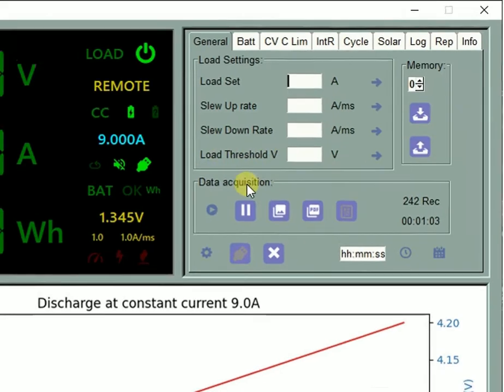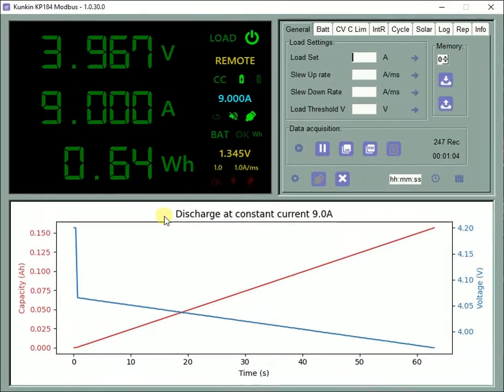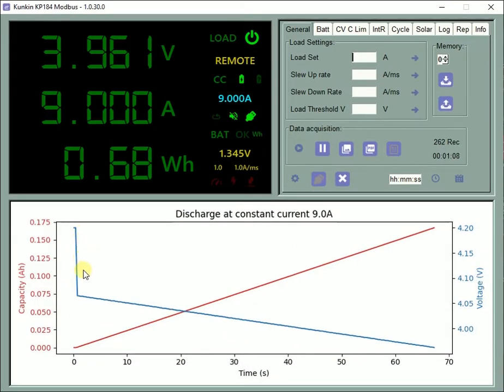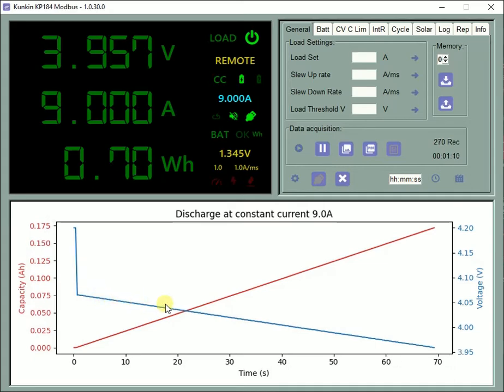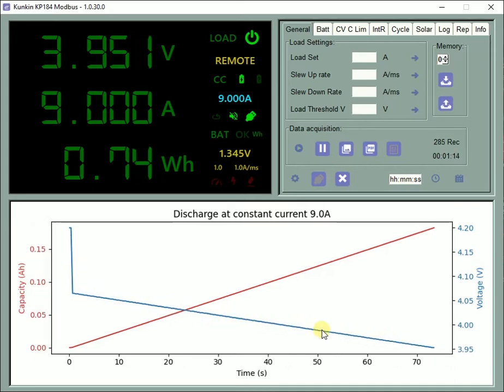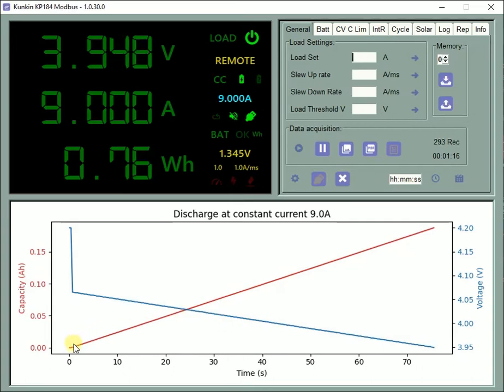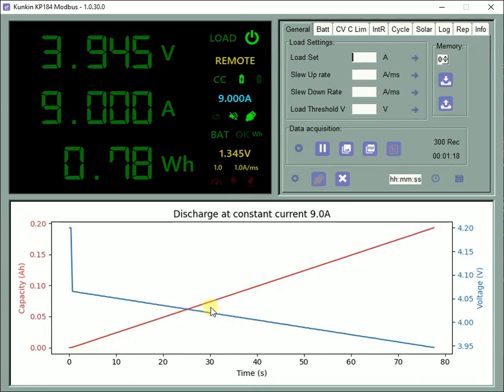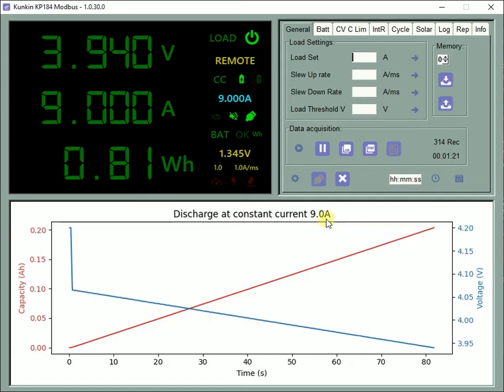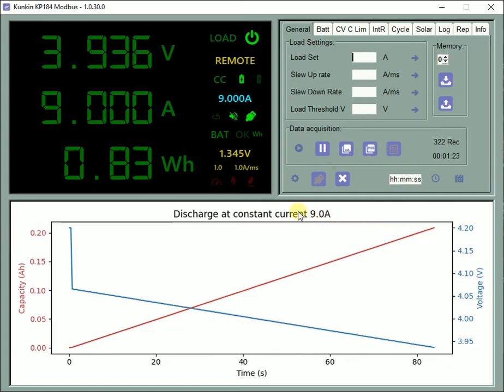At the bottom you can watch while the battery discharge curve graph is being plotted in real time. The light blue curve represents the battery voltage as a function of time. The red curve represents the test accumulated battery capacity in ampere hour.